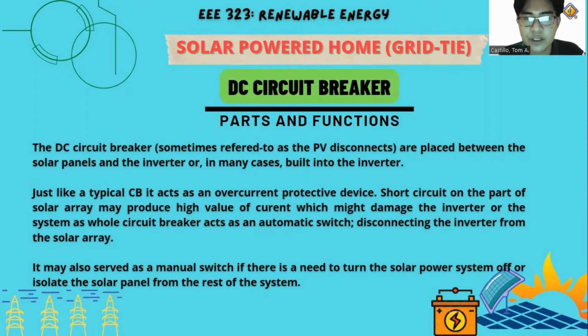The DC circuit breaker, sometimes referred to as the PV disconnects, is placed between the solar panels and the inverter, or in many cases built into the inverter. Just like a typical CB, it acts as an overcurrent protective device. A short circuit on the part of the solar array may produce a high value of current which might damage the inverter or the system as a whole. The circuit breaker acts as an automatic switch, disconnecting the inverter from the solar array. It may also serve as a manual switch if there is a need to turn the solar power system off or isolate the solar panel from the rest of the system.